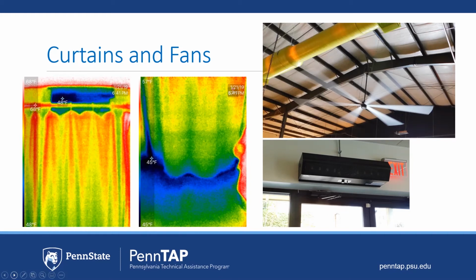Lofty ceilings in offices or warehouses can be troublesome to maintain comfortable heat. Using a high volume, low velocity fan can help your facility push hot air that has risen to the ceiling back down to the ground. A brewery installed an HVLS fan in their facility and were able to recognize over $1,500 in fuel cost savings for the winter months.